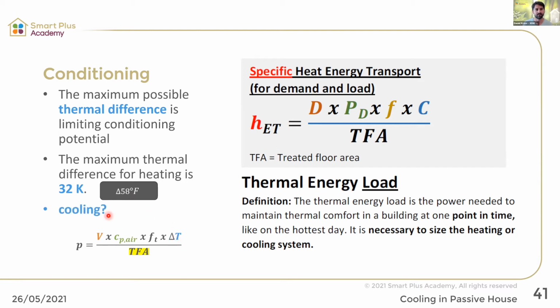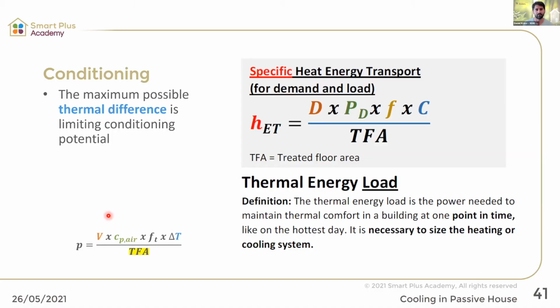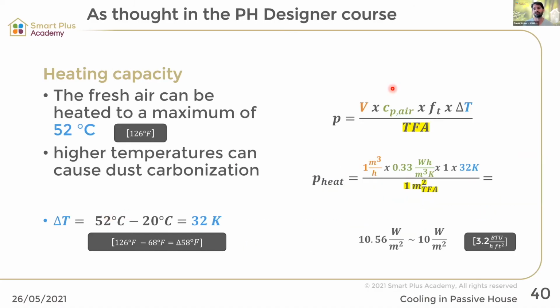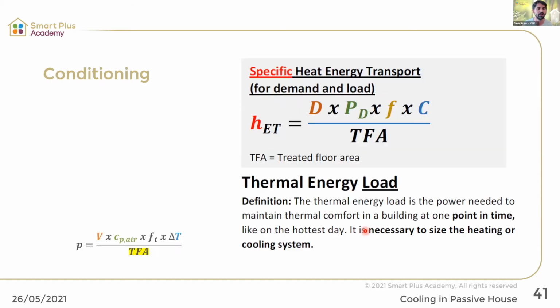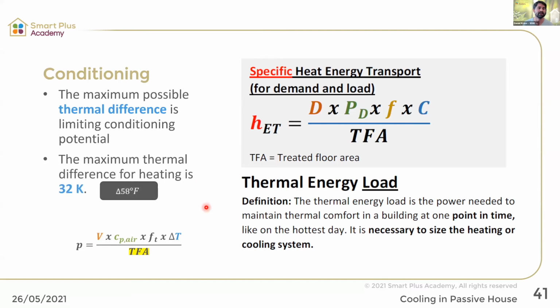What is now the situation with cooling? Actually, I jumped over that quickly here. So this is now the calculation: 1 cubic meter of air by the capacity of air, the thermal mass of air, the storage capacity of air, by the thermal difference divided by the TFA comes to this 10 watts per square meter, your 3.2 BTU per hour per square foot. Yeah, that's what comes in the standard. So on the heating side, happy days, no problem. But now we're coming to the cooling side.